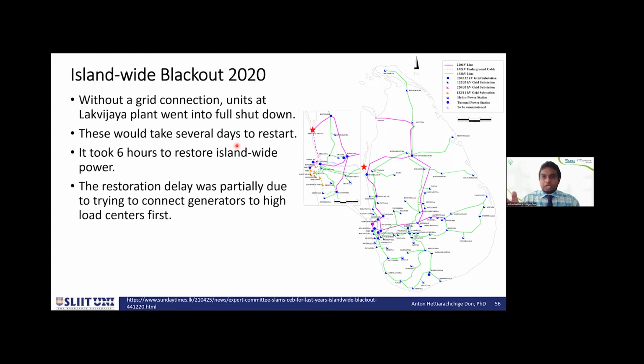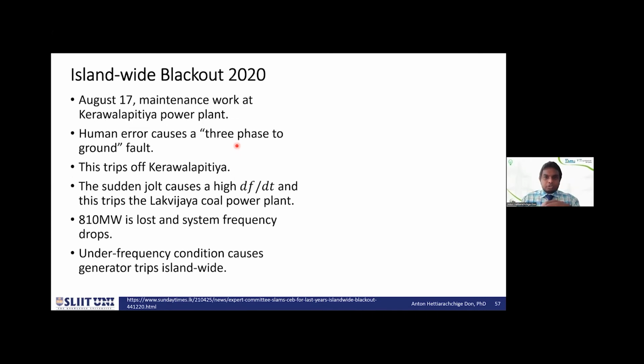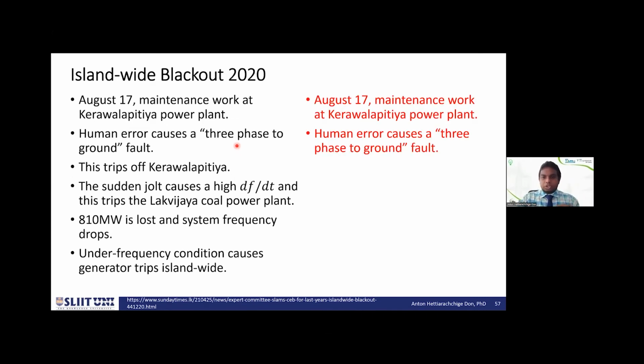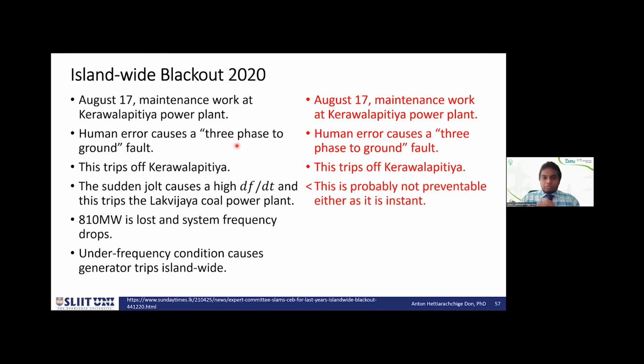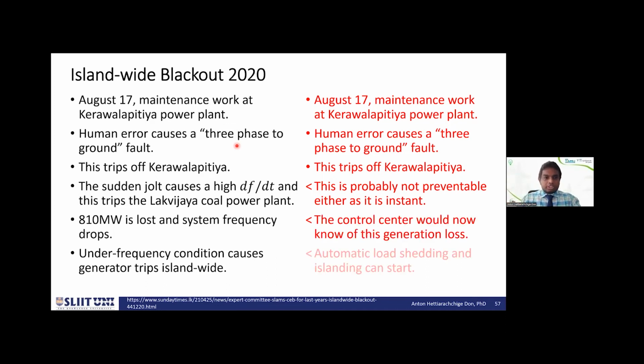This was partially because they didn't know exactly how much power was connected. So when they tried to connect to high power loads, the generator would shut off again. Okay. So how could the PMU system have prevented this? We can only speculate here. Of course, the first 2 parts we cannot prevent. Up to tripping off Kerawalapitiya, that's a human factor, a human error. We cannot prevent that. That happens. The tripping of Lakvijaya probably would also not be possible to prevent because it happened instantly. But now, this 810 loss, we know about this. PMUs would tell us, okay, we lost this much power. Within seconds, it would calculate how much power was lost. Let's start load shedding. Let's turn off non-critical loads.